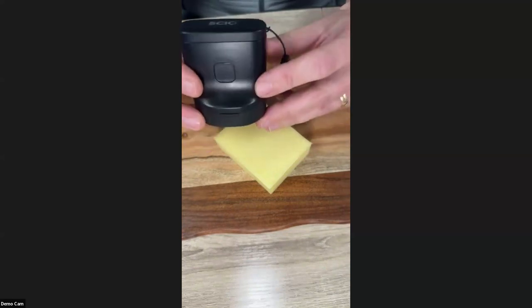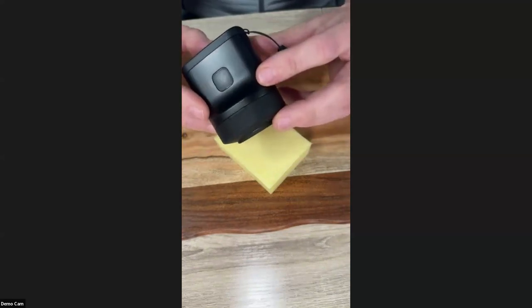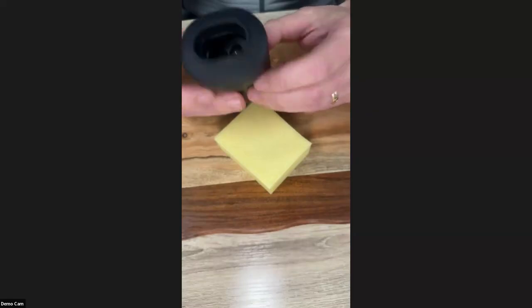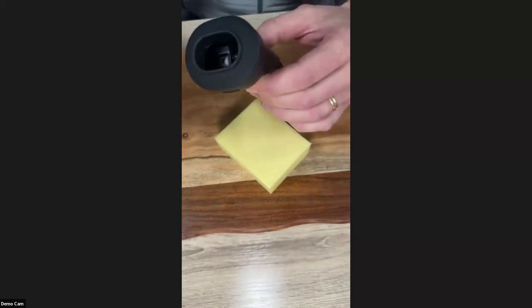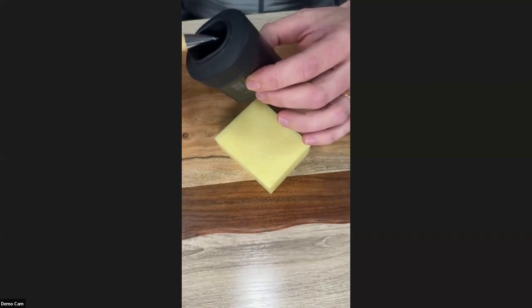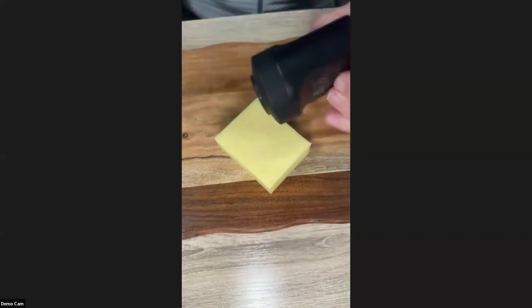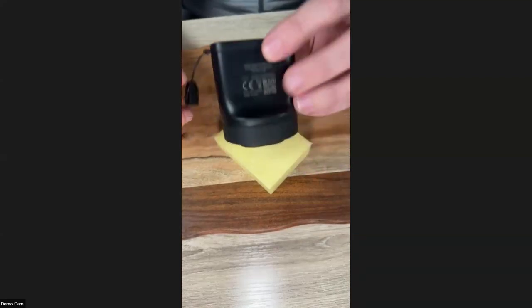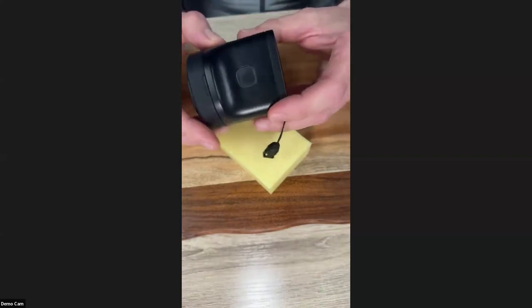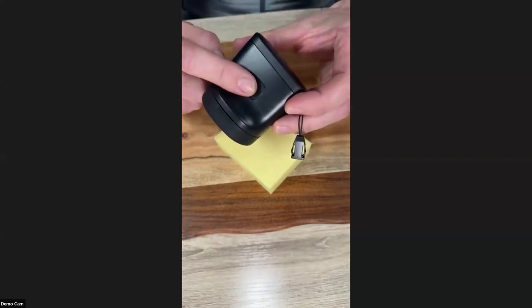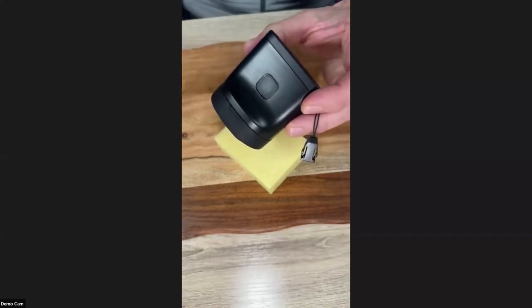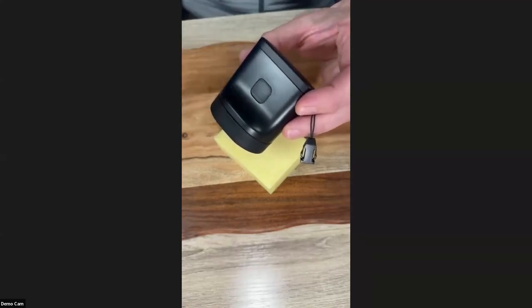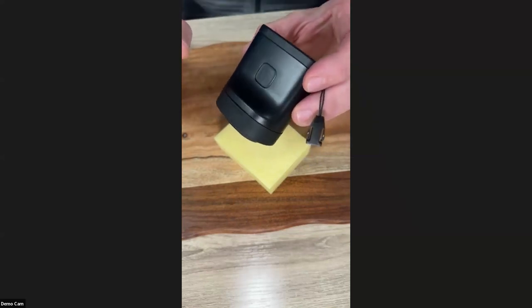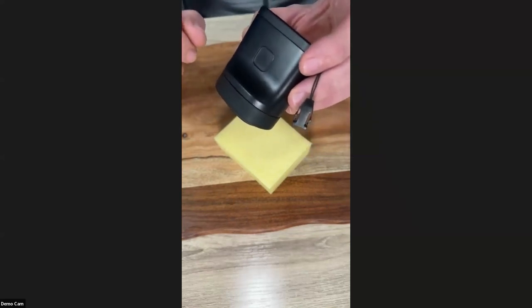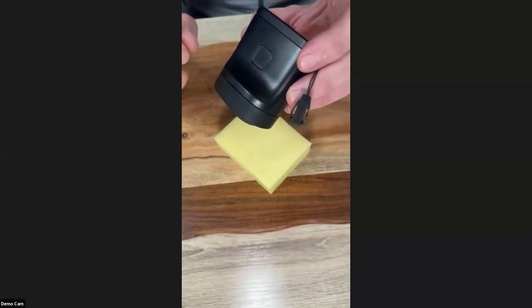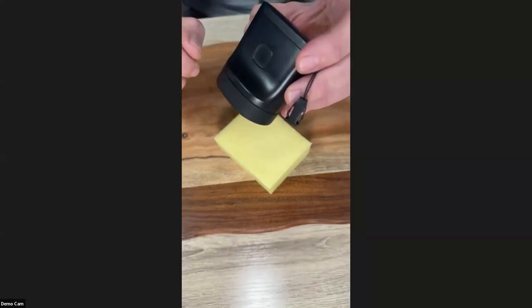All right, so you can see the unit here, portable, relatively small. There's not too many moving parts, but the business end of it is here below the shade. That's the sensor and the light source. That's what's actually going to be put on the cheese sample to read it. As Penny mentioned, there's a one button operation. It's used to turn the device on and off and to pair it. There's also a status ring around that button, which will illuminate different colors. For example, it'll start flashing white when it's ready to connect. It'll stay white when it's connected and ready to scan, and flash red for low battery.